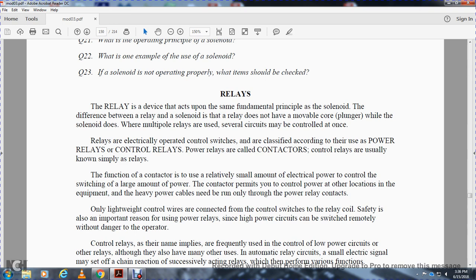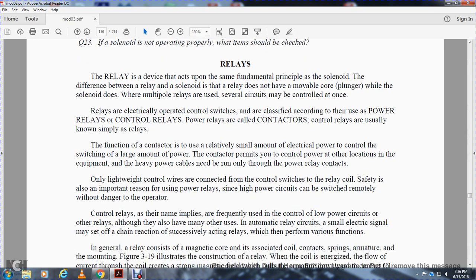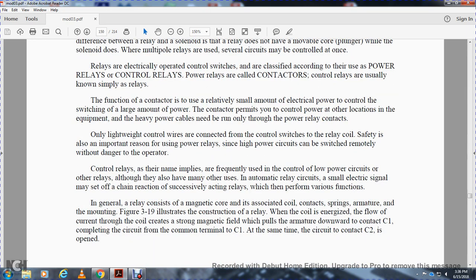Power relays are also called contactors. Control relays are usually known as simple relays. The function of the contactor is usually to use a relatively small amount of electrical power to control the switching of a large amount of power. The contactor permits the control power for other locations, including the heavy power cable, to need to run only through the power relay contacts.